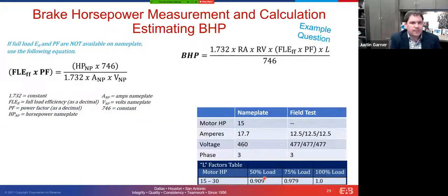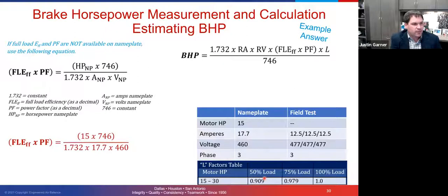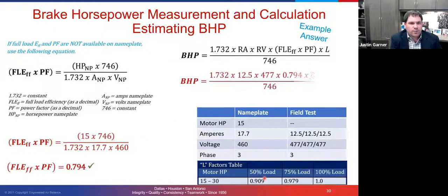And so we're gonna go through and look at this right here. This is the equation I showed you earlier. We're going to first calculate our full load efficiency times power factor, which is going to give us a 0.794. If we plug everything in there, that's pretty simple, all nameplate data.